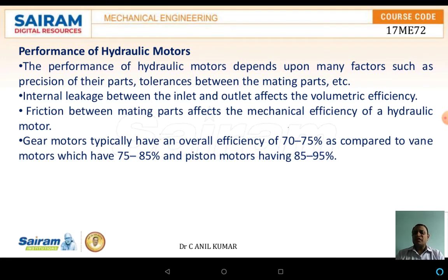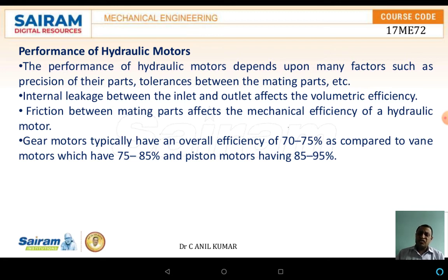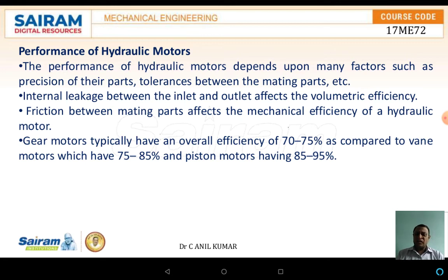The performance of the hydraulic motors depends on many factors such as the precision of their parts and tolerance between the mating parts. Internal leakage between the inlet and the outlet affects the volumetric efficiency. Friction between the mating parts affects the mechanical efficiency. The overall efficiency of gear motors varies from around 70 to 75 percent, compared to vane motors which vary from 75 to 85 percent, and piston motors which vary from 85 to 95 percent.